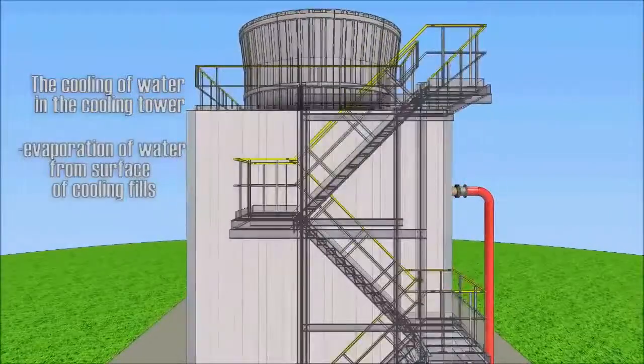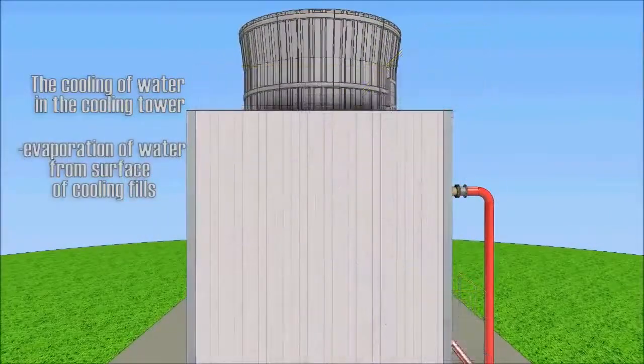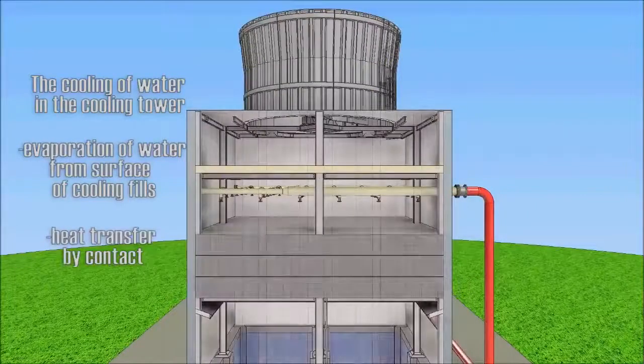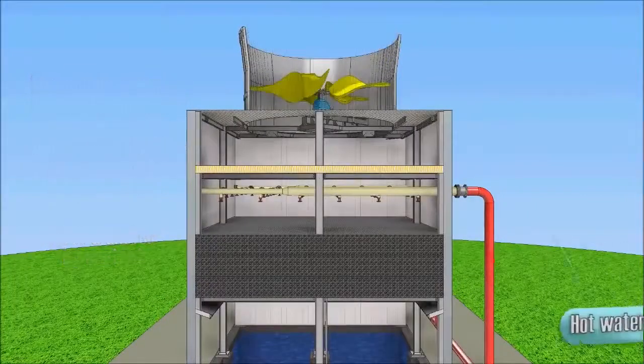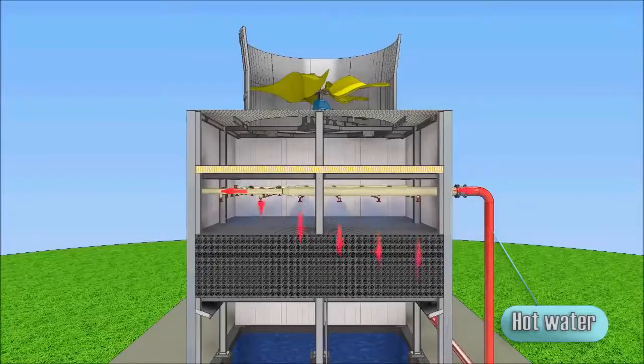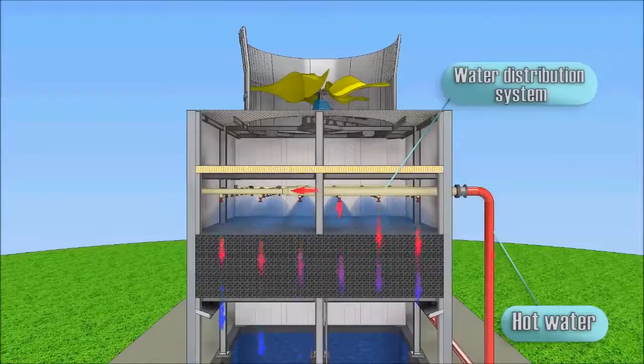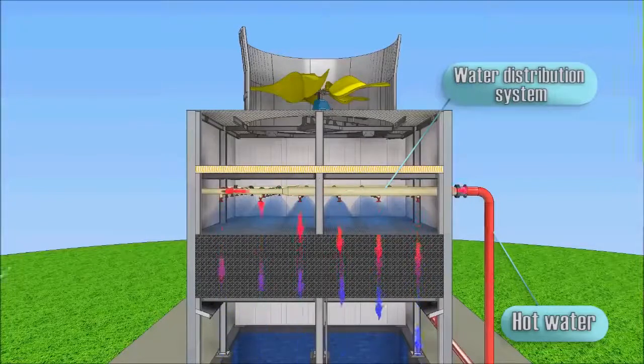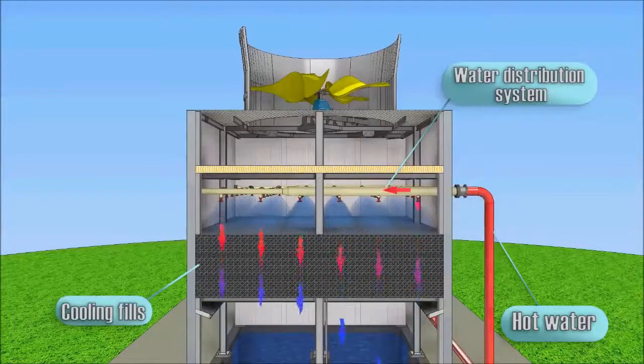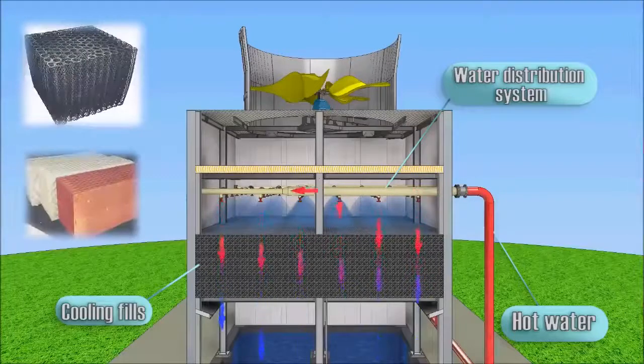Heat transfers by contact with air. Hot water from various sources such as machines or heating processes flows through pipes to the distribution system of the cooling tower, which produces even water distribution to all the area of fills by spray nozzles. On the fills, a water film is formed.